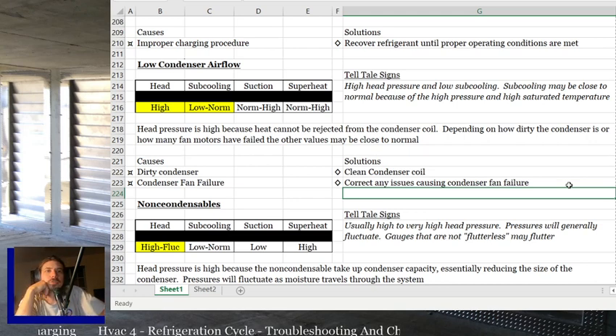If you're not sure, try spraying some water through it and see what you get out, because sometimes it looks clean, then you find all the stuff in between the coils. So high head pressure, low subcooling. Subcooling may be close to normal because head pressure and high saturated temperature. Head pressure is high because heat cannot be rejected from the condenser coil, depending on how dirty the condenser is or how many fan motors have failed.